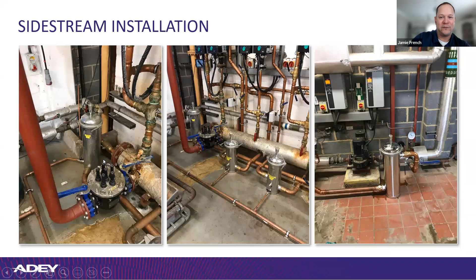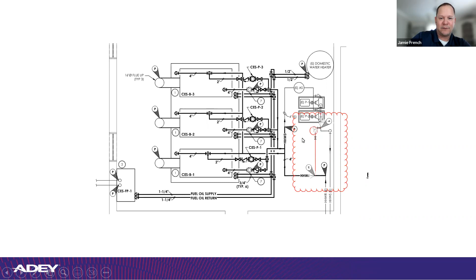What they were having problems with were all the pumps you see here. Pump here, pump here, pump here, 2 pumps here. They were failing left and right. So this engineer actually put in, where he's going to put his CMX side stream filter across the supply and return right next to the pumps there, to get that magnetite out of the system.